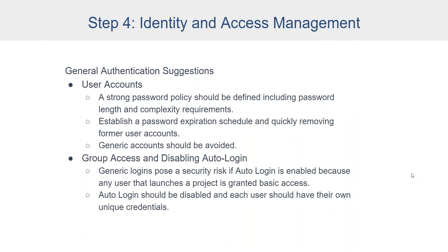A couple of general authentication suggestions: when it comes to user accounts, a strong password policy should be defined, including password length and complexity requirements — passwords may need to include letters, numbers, and special characters. You should also establish a password expiration schedule and quickly remove former user accounts when people leave the company. Avoid using generic accounts — people should log in as individuals, not as a shared 'operator' account. Auto login should be disabled and each user should have their own unique credentials.